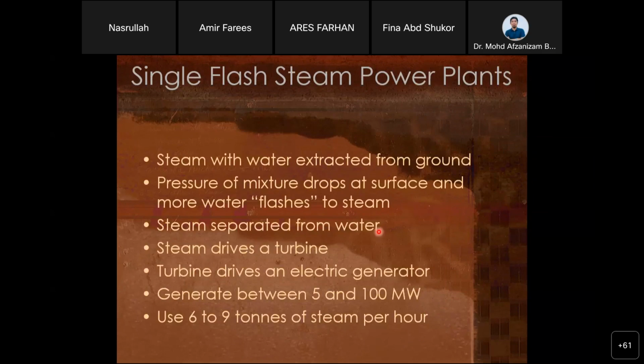This is the storyline mentioned just now: steam with water extracted from the ground, pressure initial drop at the surface, and more water flashes to steam. Steam separates from water, steam drives a turbine, turbine drives an electric generator. As mentioned, it generates between 5 and 100 megawatts, using 6 to 9 tonnes of steam per hour. Depends on how good your system is to extract, capture, and collect the steam, and that may refer to your range of generated power.